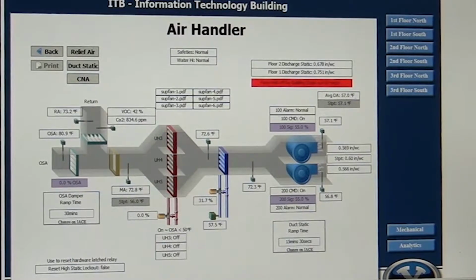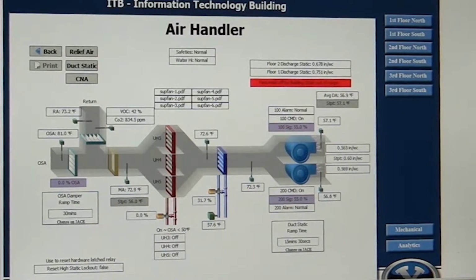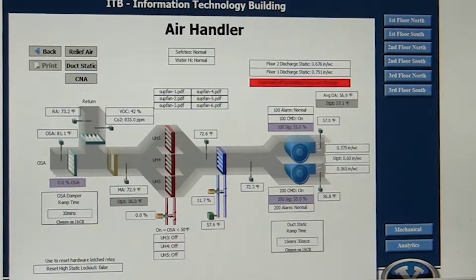We start hitting cool mornings where we've got 55, 60-degree air. If you put it on full outside air, you can still keep the building comfortable and run all your sensors so they're calibrated. Does that make sense? Okay.